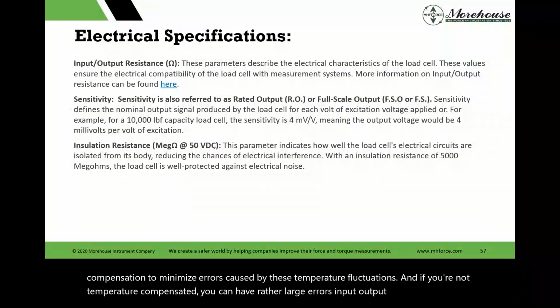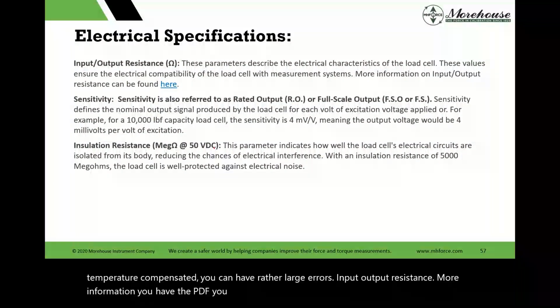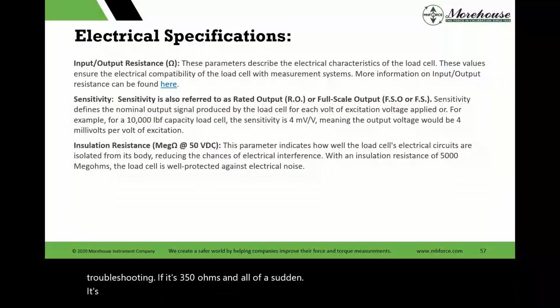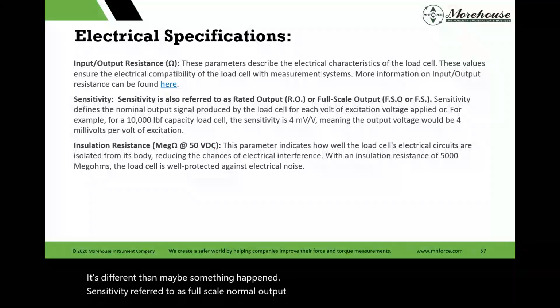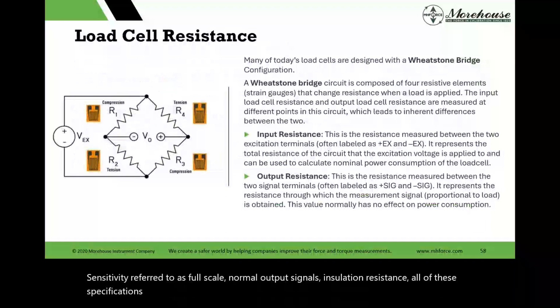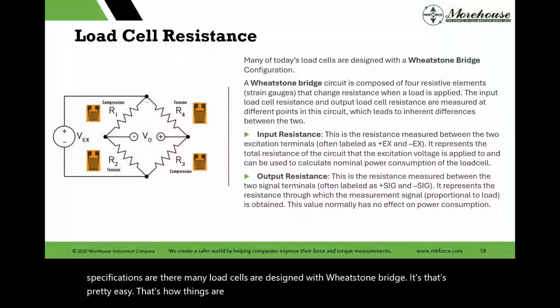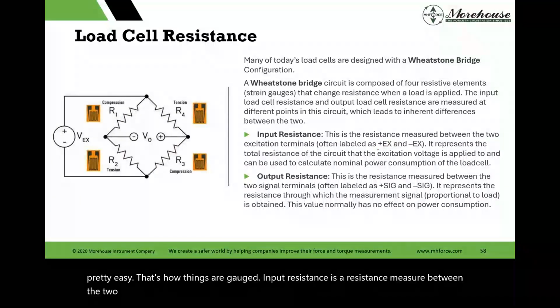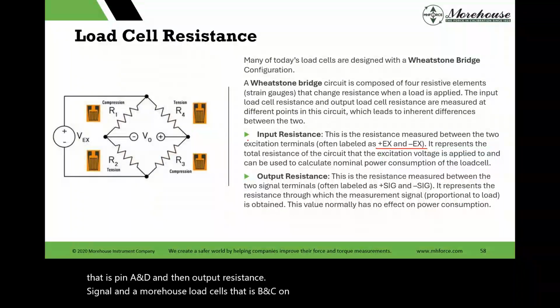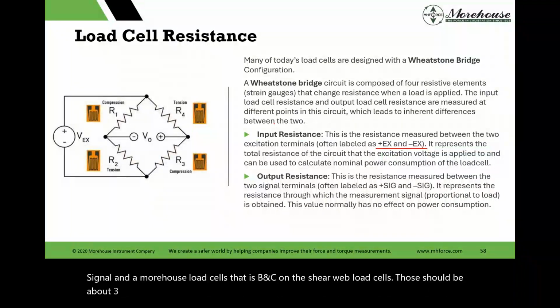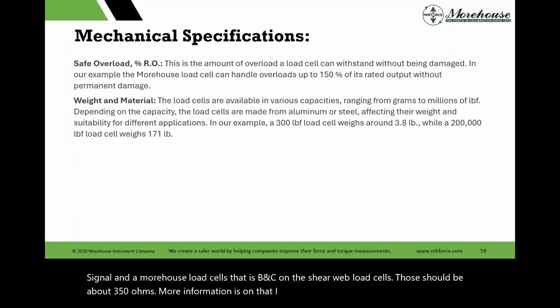Input output resistance, more information: you have the PDF, you can look at this. It's electrical characteristics, useful in troubleshooting. If it's 350 ohms and all of a sudden it's different, then maybe something happened. Sensitivity referred to as full scale, normal output signals, insulation resistance, all of these specifications are there. Many load cells are designed with a Wheatstone bridge. That's pretty easy. That's how things are gauged. Input resistance is the resistance measured between the two excitation terminals, positive excitation, negative excitation. On Morehouse load cells, that is pin A and D, and then output resistance is your signal, and on Morehouse load cells, that is B and C. On the shear web load cells, those should be about 350 ohms. More information is on that. I wanted to make sure we talked about everything.